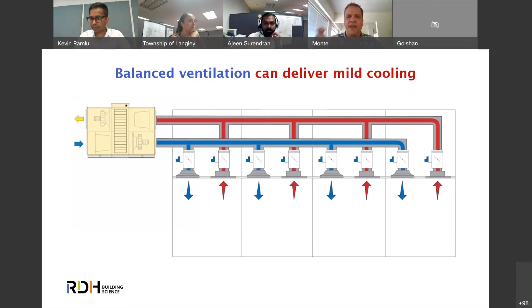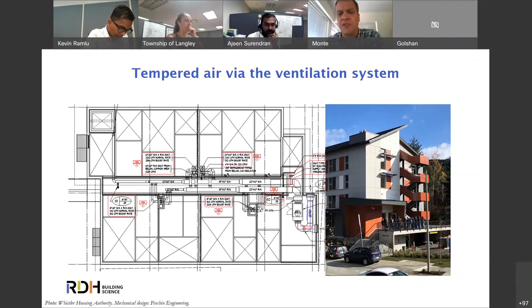Whistler Housing built Passive House workers housing in Whistler, and it's one of the first projects to use that tempered air cooling. It also provides tempered air heating through the whole system. It was less expensive to install the central ERV with cooling than it was to put in 24 local ERVs, one in each unit. So, less construction cost, easier to change the filters because you have a central system rather than having to enter each unit to change all those filters, and the ability to add heating, cooling, and in muggier climates, dehumidification, which is a major issue, though not so much in Whistler.